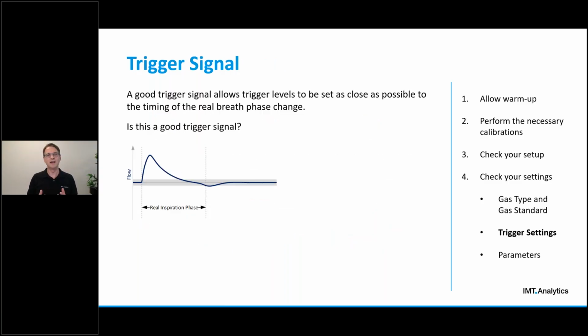So the first and main challenge with trigger settings is to find a good trigger signal for our trigger levels. The question is, what characterizes a good trigger signal? The answer is, a good trigger signal allows trigger levels to be set as close as possible to the timing of the real breath phase transitions. That sounds logical, right? When the breath detection of your analyzer is as close as possible to reality, it will be able to measure breath-based parameters as accurately as possible. But what does that mean specifically?